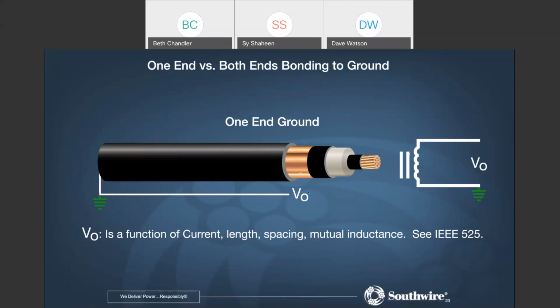So on this side, if you do open it, you're going to have an open voltage right here, which is not the end of it. That's fine, and you can calculate the open voltage. There are methods of calculating it. Obviously the longer the cable, the higher the open voltage, and it depends on the current too. The higher the current, the higher this number is. Again, it's not the end of the world. There's absolutely nothing wrong with that.